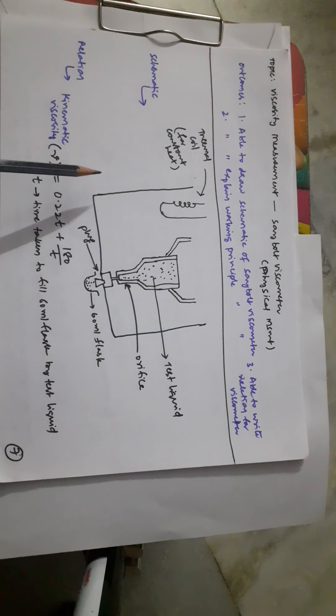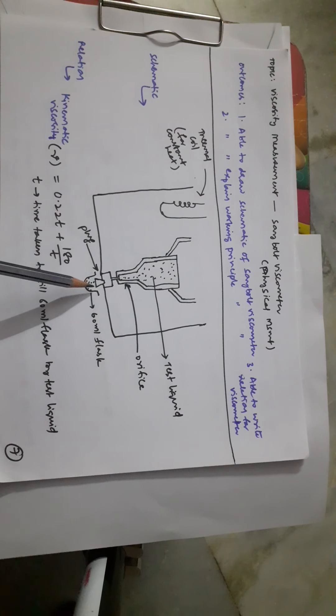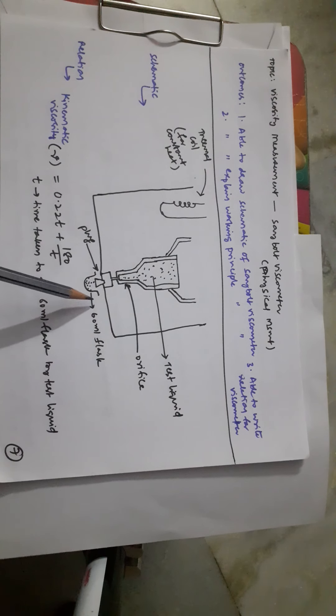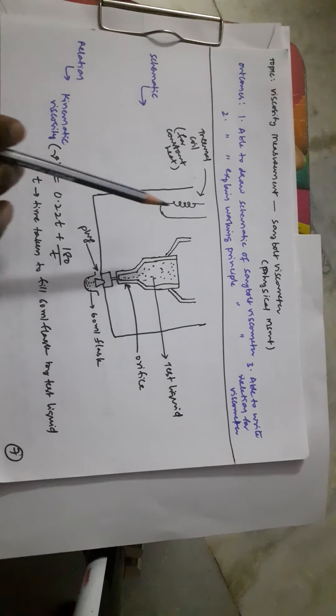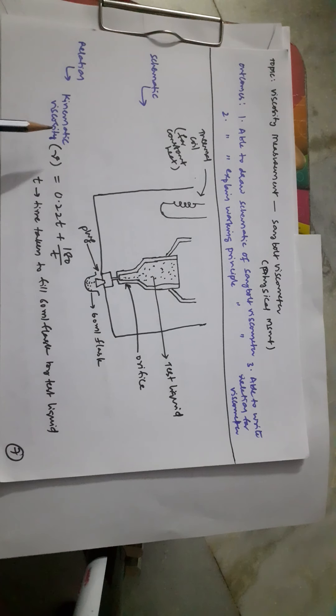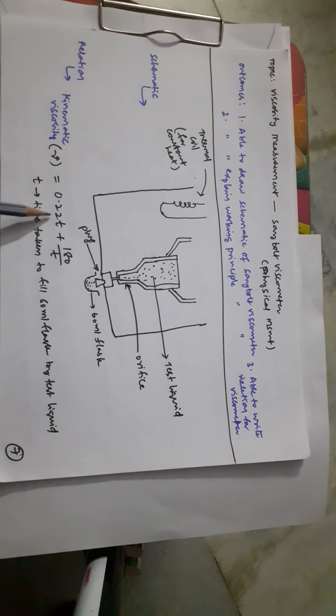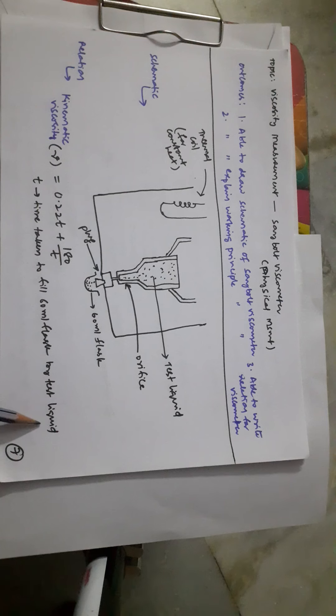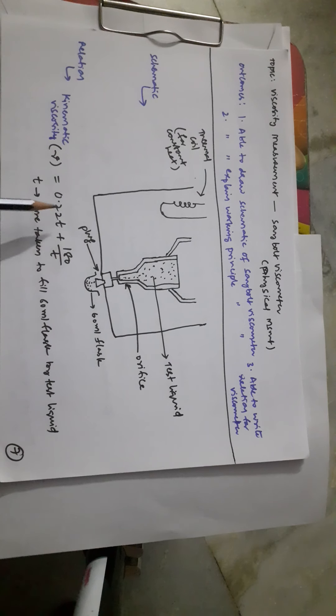Using a plug, we can start or stop the filling of a 60 ml flask. A stopwatch is used to observe the time taken to fill the 60 ml flask — open the plug to start filling, and stop the stopwatch once the flask is filled. A thermal coil maintains constant heat. The relation for kinematic viscosity is: ν = 0.22t + (180/t), where t is the time taken to fill the 60 ml flask. This relation was experimentally defined and validated by Saybolt.